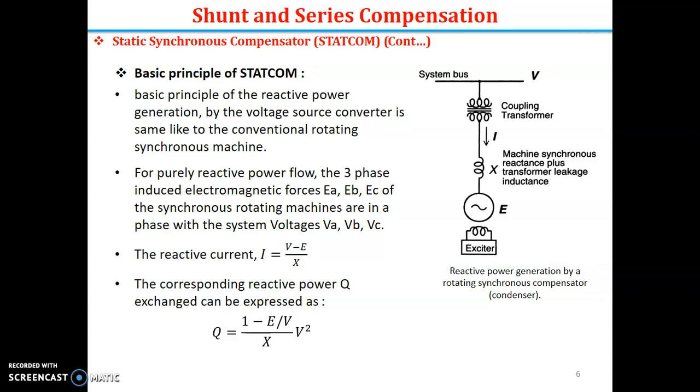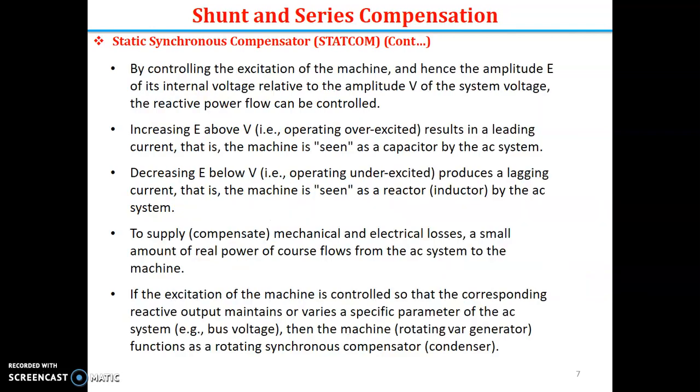Generally we require to use fully controlled switches. For low frequency applications we prefer GTOs, and for high frequency applications we prefer IGBTs, and for this reason we require to connect a coupling transformer that essentially reduces the operating voltage of the device. This is the rotational solution of the synchronous condenser, and we have the same thing, but it will be replaced by static switching devices called STATCOM.